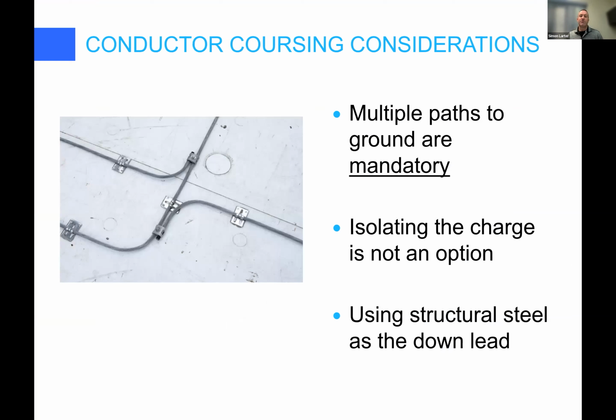What happens when we run that cabling? Well, we don't want to bend it and we don't want to kink it, because that introduces resistance into the cabling. So every bend we make has to be a nice sweep. 8 inches radius is the number we are looking for, 200 millimeters. We don't want a tighter radius than that. And we also don't want a 180-degree turn. We want to make a sweep. 90 degrees is as much as we want. We just want to make sure lightning has a nice smooth path to ground. We don't bend, we don't kink.